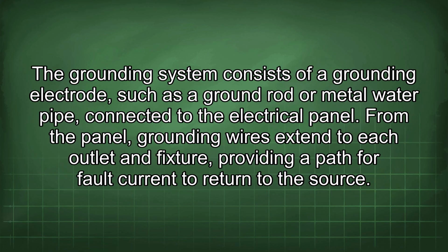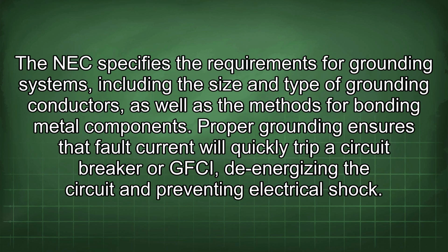The grounding system consists of a grounding electrode, such as a ground rod or metal water pipe, connected to the electrical panel. From the panel, grounding wires extend to each outlet and fixture, providing a path for fault current to return to the source. The NEC specifies the requirements for grounding systems, including the size and type of grounding conductors, as well as the methods for bonding metal components. Proper grounding ensures that fault current will quickly trip a circuit breaker or GFCI, de-energizing the circuit and preventing electrical shock.